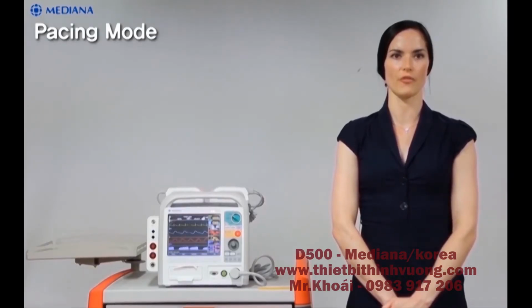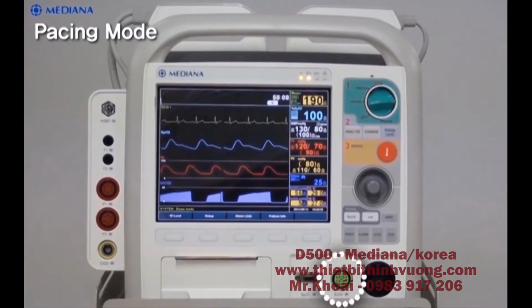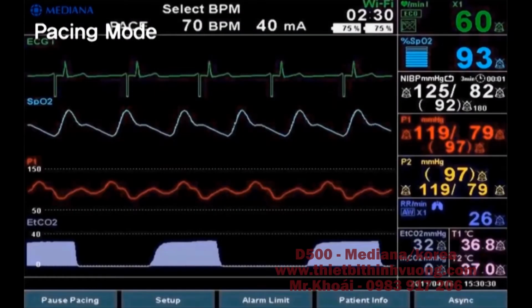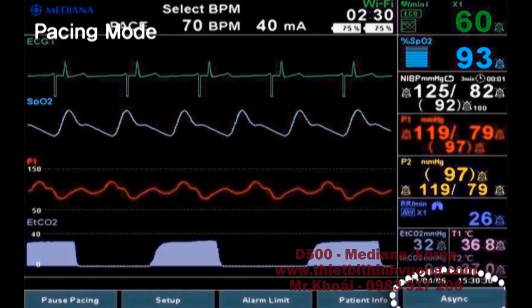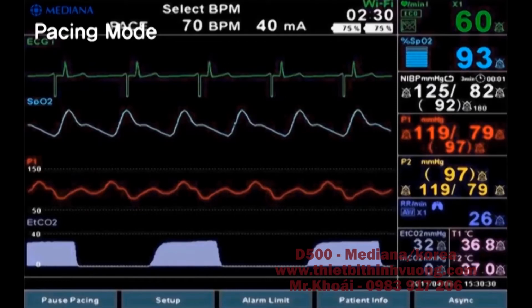When the selected value of pace pulses per minute or a value below is detected, the relevant current is delivered to the patient. Please note that the ECG cable must be directly connected from the patient to the defibrillator monitor while pacing in sync mode. If you want to activate async mode, press the async soft key located in the lower right corner of the screen. And if you want to pause the pacing, press the pause pacing soft key located in the lower left corner of the screen. To resume pacing, press the pause pacing soft key again.